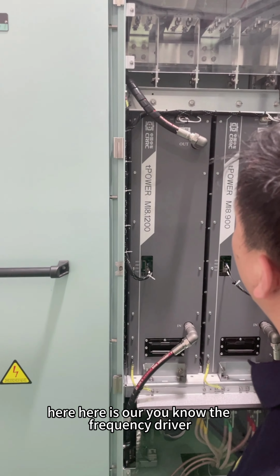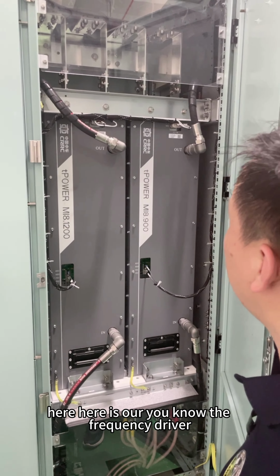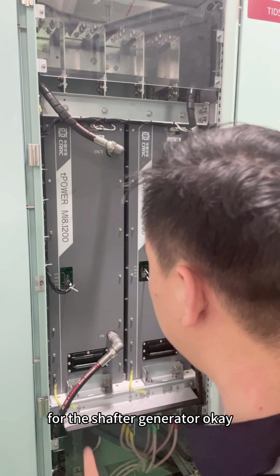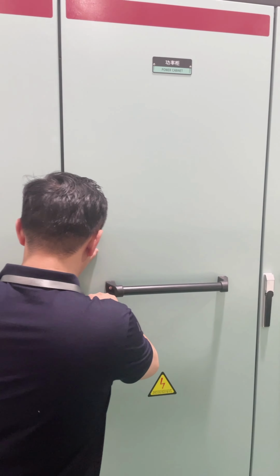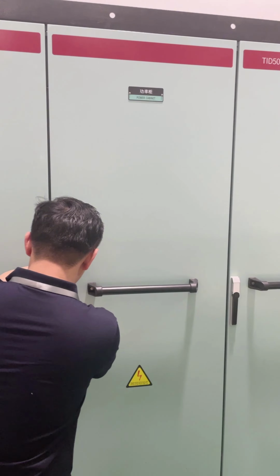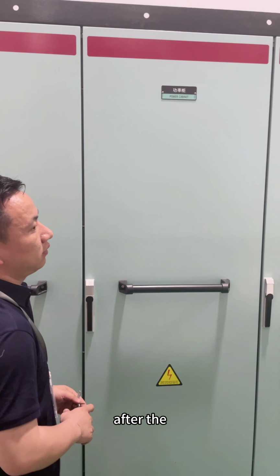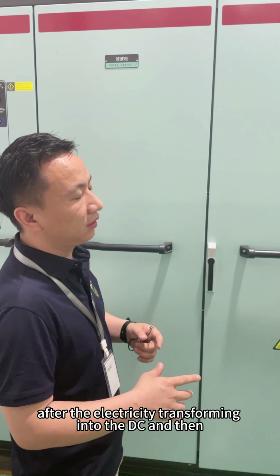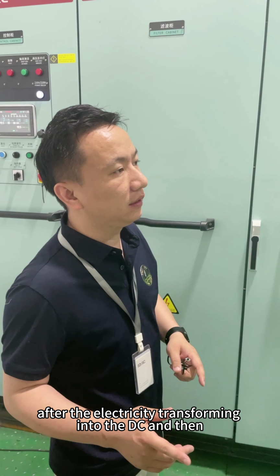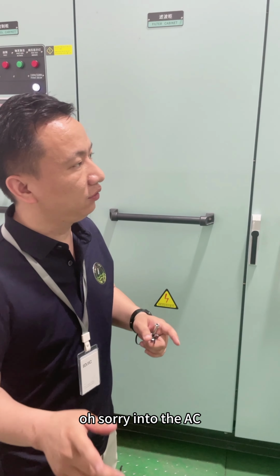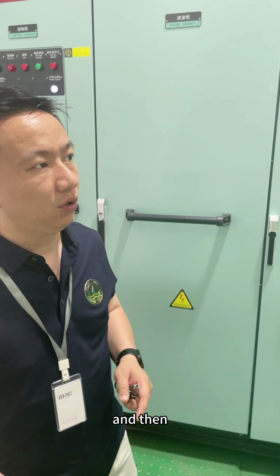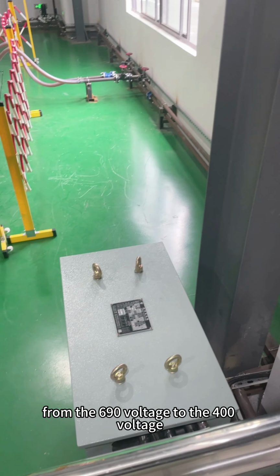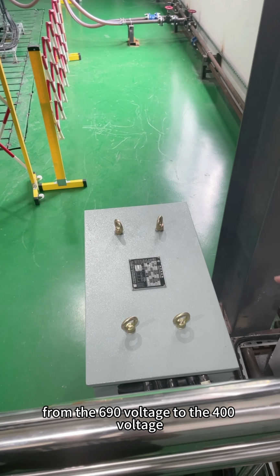Here is the frequency driver for the shaft generator. After the electricity is transferred into DC and then into AC, we transfer the electricity to here. Here's our transformer from the 690 volts to the 400 volts to adapt to the grid on board.